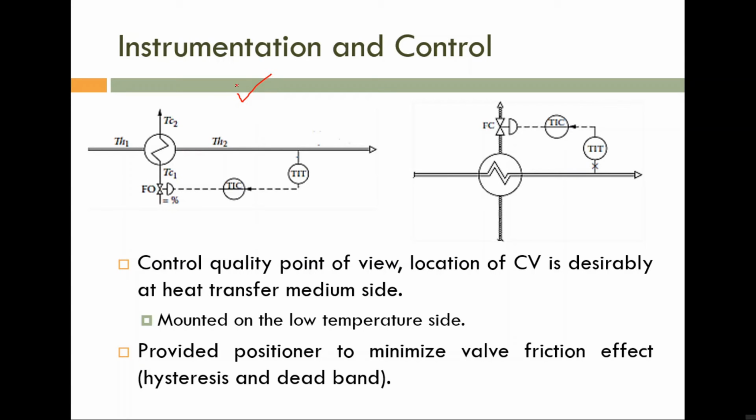If you are considering a cooler, you can see that the control valve is installed at the input side. If you are considering a heater, the control valve is installed at the output side. The reason is that we are using a control valve to manipulate the flow rate. If you are using a control valve, then its size is very, very important.